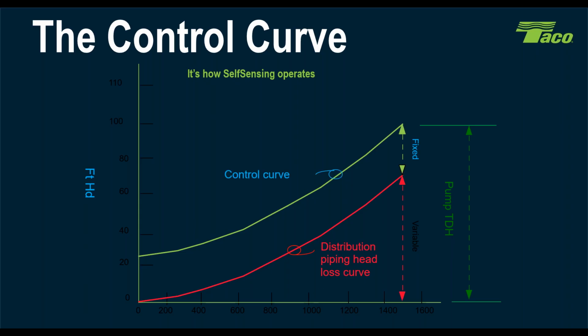And the control curve is what self-sensing is actually going to operate to. It very closely imitates the system curve. However, it's additive because it picks up the set point pressure, that differential that we know we have to maintain out in the system. And those two together is how self-sensing actually works, because we know that as we increase and decrease speed and flow, we've got to maintain the same set point pressure. But we know that system curve, that distribution piping head loss curve, is infinitely variable depending on how much water we're moving.